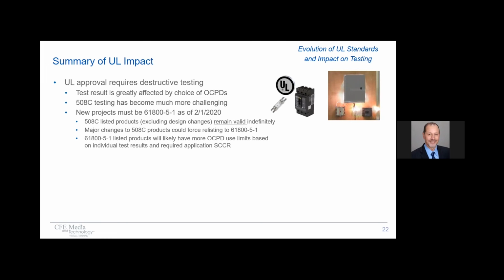As I mentioned, there's been major changes to 508C, or I should say that major changes to a product could require that products that are presently listed under 508C could be forced into the new standard because there may be design changes to those products. And lastly, the new standard, 5-1, those listed products will likely have more use limits when it comes to protective devices and things like withstand ratings.